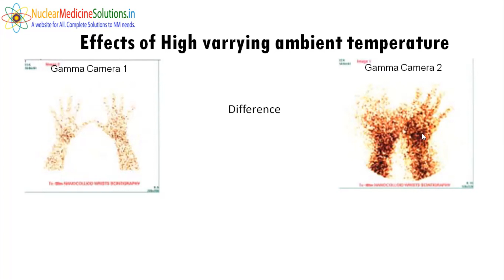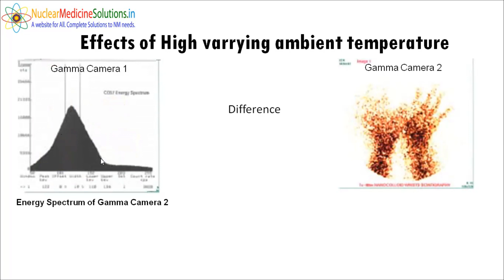The image becomes bad, and the energy spectrum also becomes broad. When we performed the uniformity test of that gamma camera 2, the uniformity also became worse, showing non-uniformity in the image. The spatial resolution of that gamma camera also degraded. So ambient temperature also affects your image quality. Always keep the ambient temperature between 20 to 22 degrees centigrade.